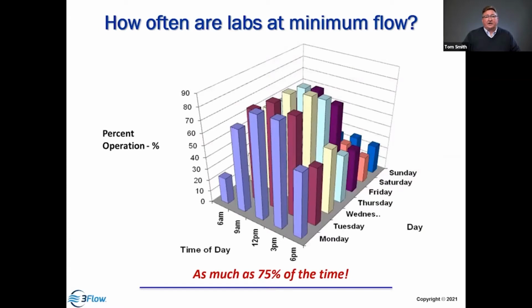Knowing how those occupants use the labs is really important. If we were to track the occupants and utilization of the labs over time, we may see that it's not always consistent. People like to say, oh, they work 24 hours a day in the lab. Well, that's not reality. We have a work week that's typically 2,080 hours a year. That's Monday through Friday, say 8 to 5, right? If you're working more than 40 hours a work week, well, maybe that time goes up, but there's 8,760 hours in a year.